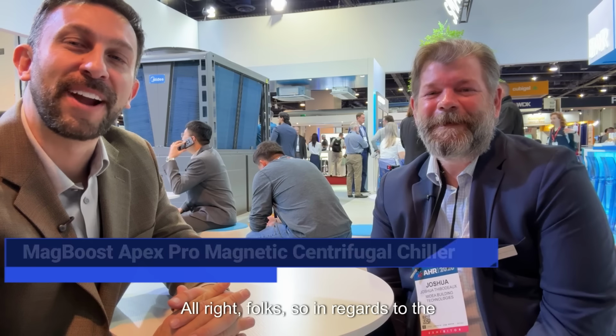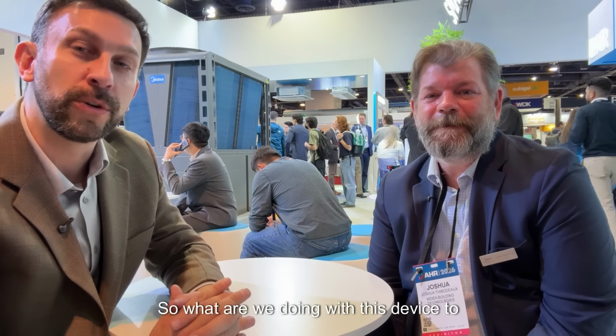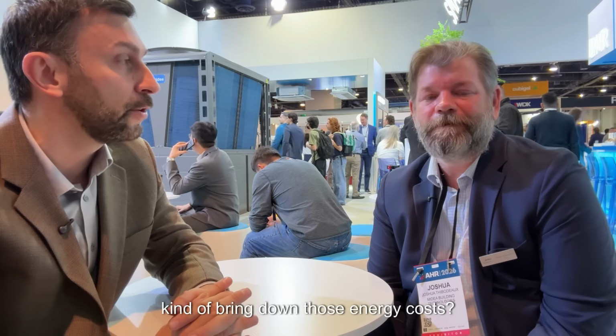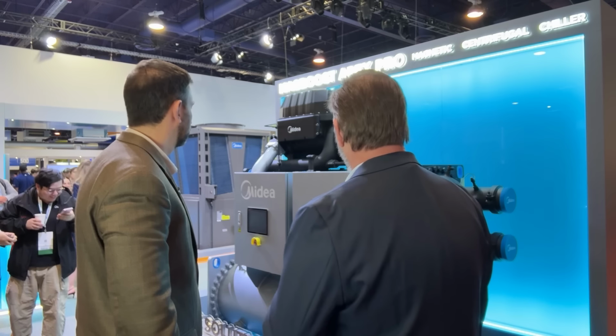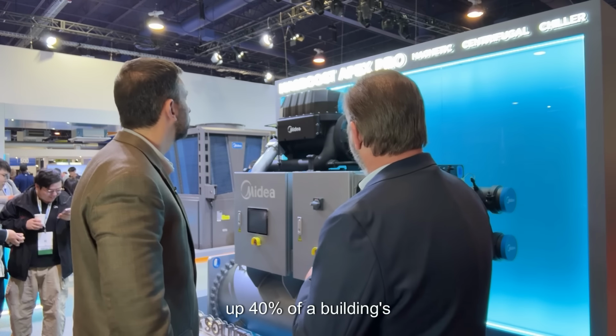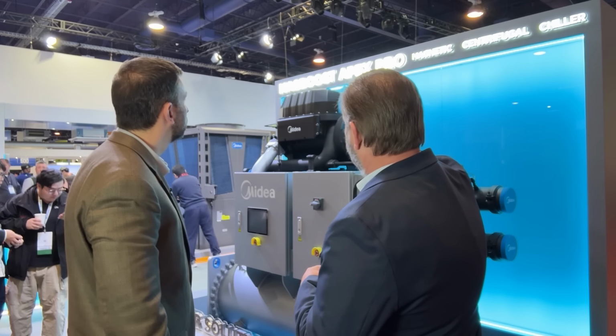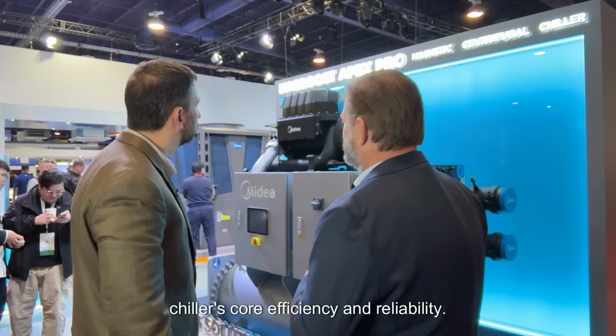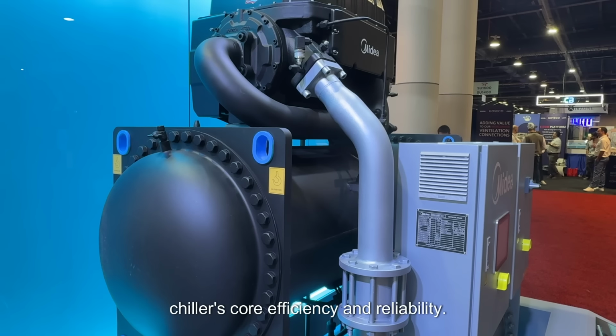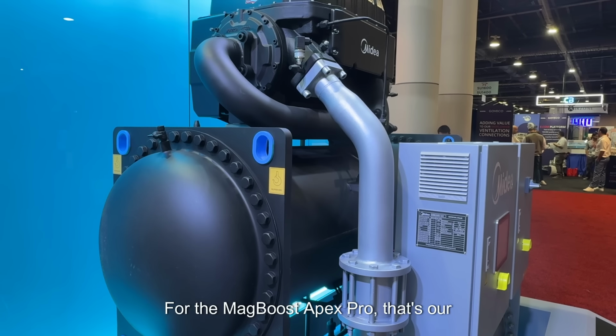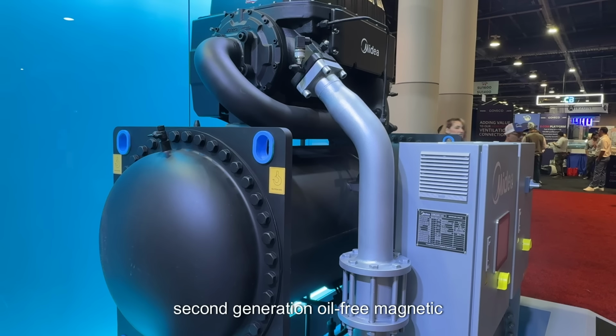In regards to the MagBoost Apex Pro, energy is a big issue with large buildings, so what are we doing with this device to bring down those energy costs? Cooling can eat up 40% of a building's energy cost, so the real breakthrough had to be in the chiller's core efficiency and reliability. For the MagBoost Apex Pro, that's our second generation oil-free magnetic bearing.